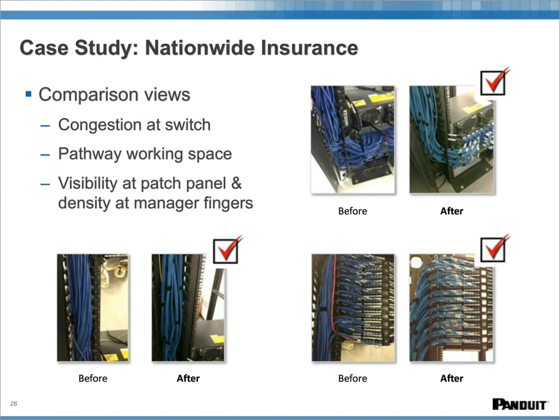Perfect. And Dan, what about looking at the last set of pictures in terms of the patching into the panels? We talked about the visibility at the panels and the density at the vertical manager fingers of the cabling. Any comments there? Yes. Well, you can see it's a lot cleaner. It's a lot nicer. It's not bundling up a lot in the fingers on the vertical managers. Great. So we'll count that as a win too.